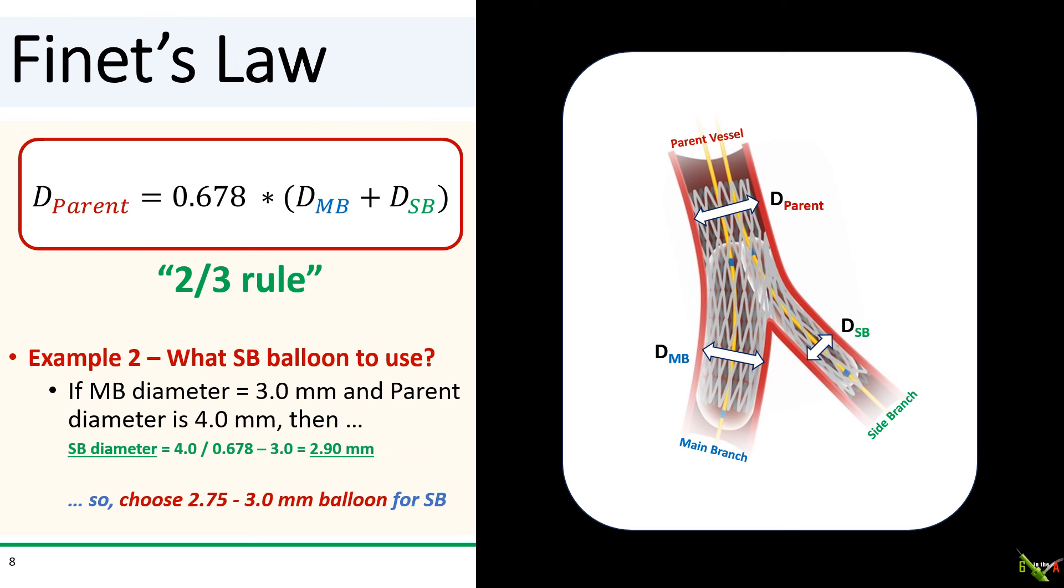And here's another example. Suppose you were trying to decide the size of your side branch kissing balloon, and you've determined, say, by OCT, that the main branch was 3.0 millimeters and the parent vessel was 4.0 millimeters. Well, in this case, Finet's law will tell you that the side branch diameter should be 2.9 millimeters. So that means that you should be choosing either a 2.75 or a 3.0 millimeter balloon for kissing angioplasty in the side branch.